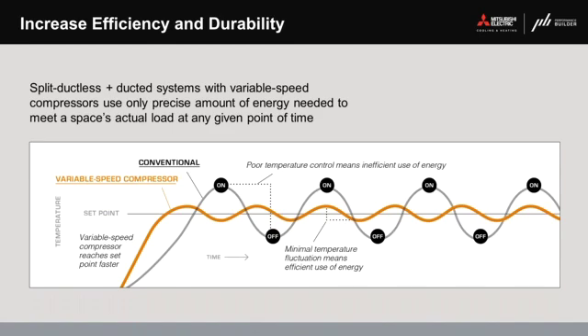Let's talk about how our systems operate and why variable capacity heat pumps fit this current building market, where we've got much lower load homes. On a high level, conventional equipment just doesn't come small enough to meet the load needs of higher performing buildings, whereas variable capacity heat pumps come as low as 6,000 BTUH, or half a ton cooling capacity. That's a better fit for a lot of these low load homes.